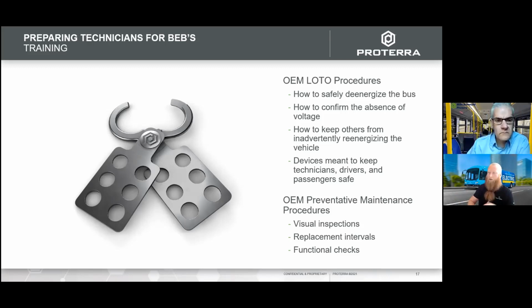However, we do not recommend using this device on the vehicle. We recommend using a cable cinch lock multi-device so that the lockout switch, our master disconnect switch, as well as the service switch at the high voltage junction box, cannot ever be turned. You pull it tight enough that the switch can't be turned and re-enabled inadvertently. With this other type of lockout device, there's a little bit of play, so it would not be the right device to make sure nobody re-energizes the circuit.